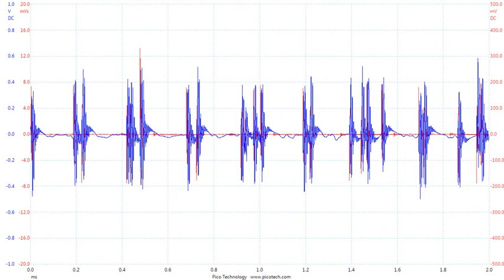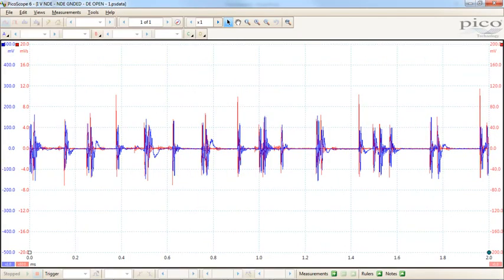Okay, that's the same. I just want to see if I can find the... Okay, here. This is the only voltage of the non-drive end with both brushes open circuited. So there's no earthing on this. Both brushes are open, but it's coupled to the load, so it's still got some form of grounding. It should have. And look at the voltage that you're measuring.